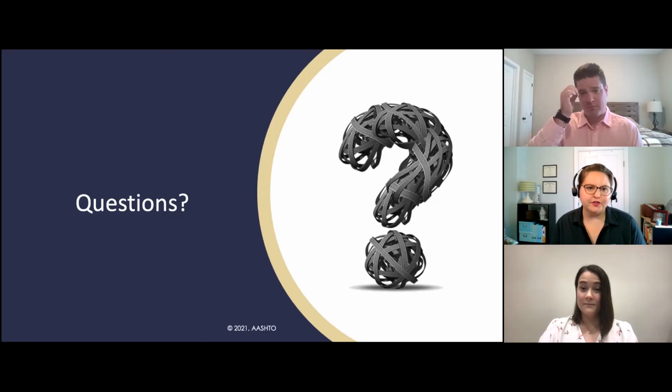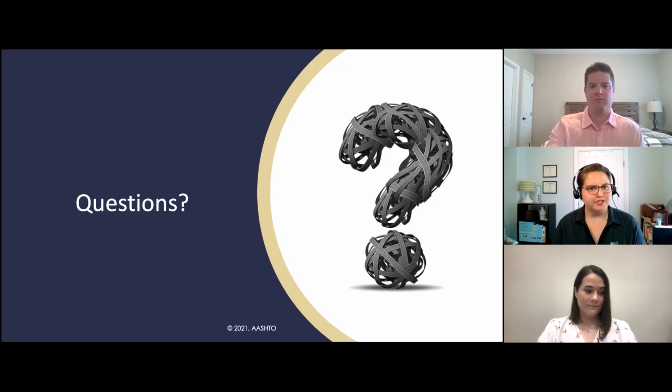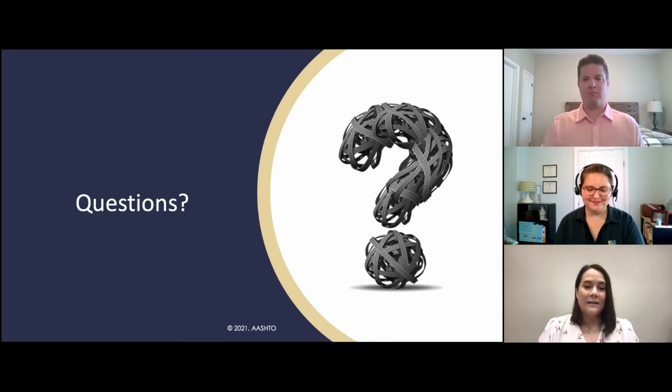Sonya, our next question is for you. Do we need to submit the last calibration, or do you want to see all the previous calibrations, or just the last 2 or 3 calibrations for equipment? Oh, this is a great question. So for remote assessments and on-site assessments, we need to see all of the current calibrations and standardizations.